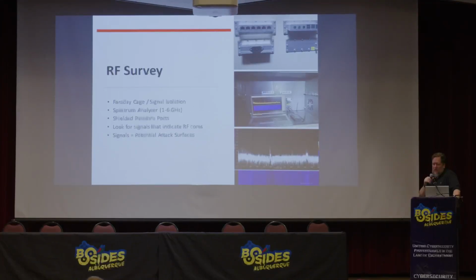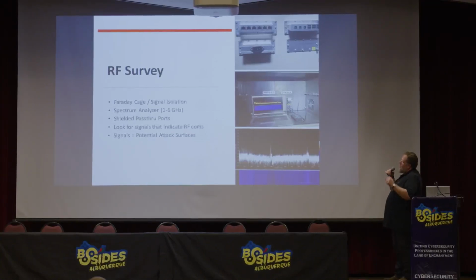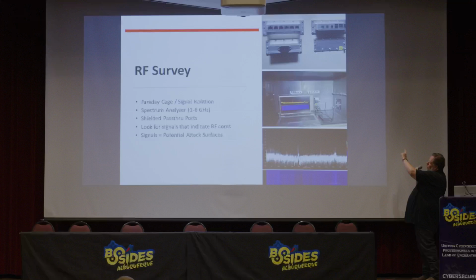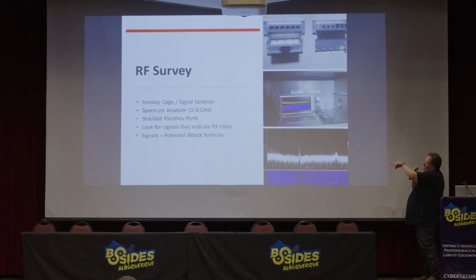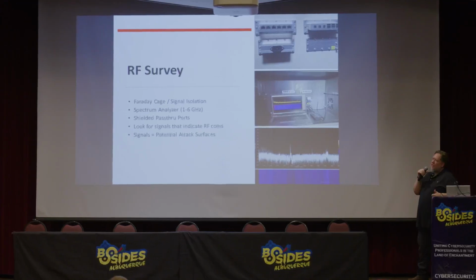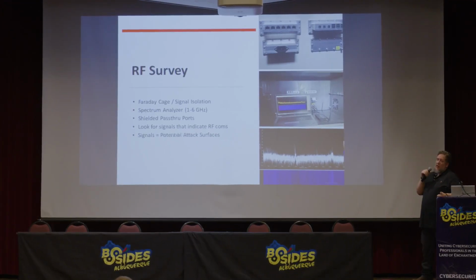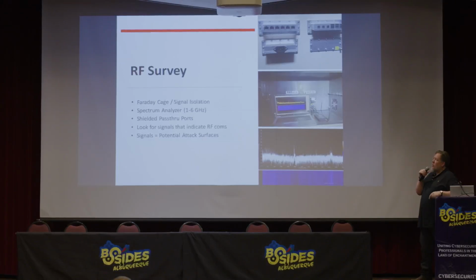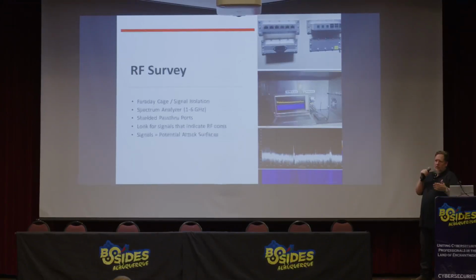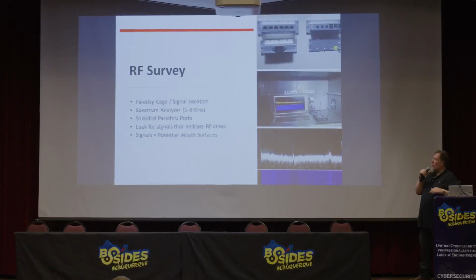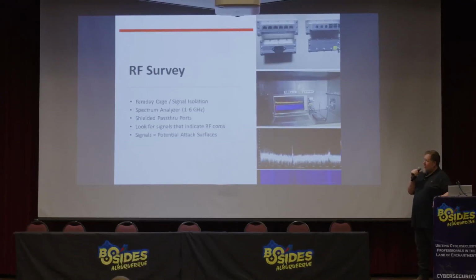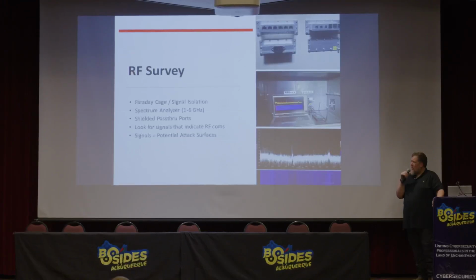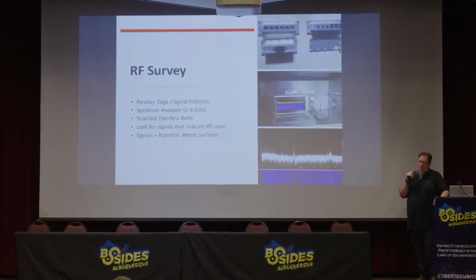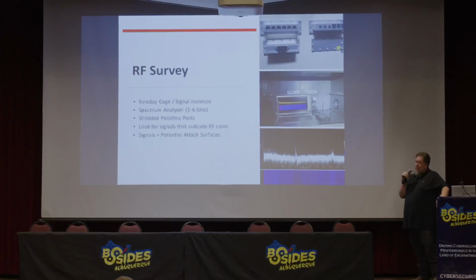So for the RF survey part of the testing, we have an isolation Faraday cage. Normally we don't have a laptop in the cage, but it made it easy to demonstrate and photograph. And so you would put your hardware device in here. There's ports for antennas, SMA ports, and then you're going to measure a few different things. You want to see what the device does when you power it on. Does it make any radio communications? You also want to see what the device does in normal operation. So user interacting with it, connecting to it over the network, does it generate any emanations there? And so we use a spectrum analyzer. Our Faraday cage goes up to 6 gigahertz. We typically don't see too many devices going above that, but it is possible.